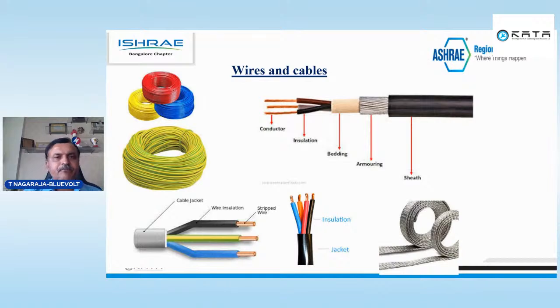Then wires and cables. I think you have seen armored cable. Armored cable is a multi-layer cable. If you see, there is the conductor, then insulation, some bedding, then armoring, then the sheath. Whenever you are doing a gland, what people will do is cut the armor, put in the PVC gland and easily connect. Please, the armor is used for earthing purposes. Whenever you are using armored cable, please use metal or brass glands so that your earthing will be intact.